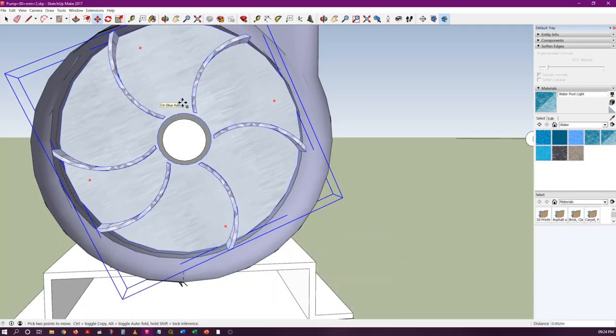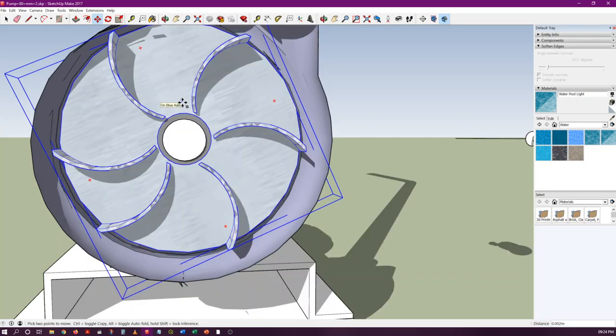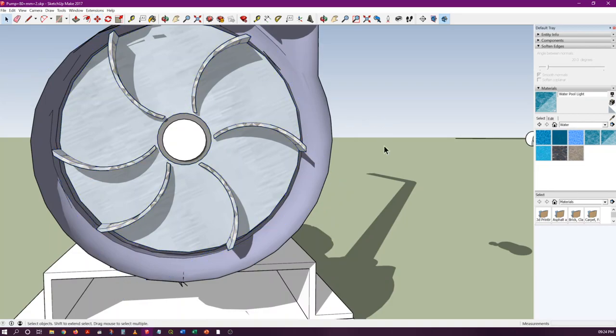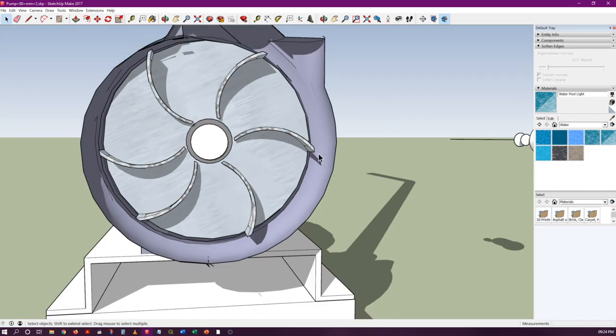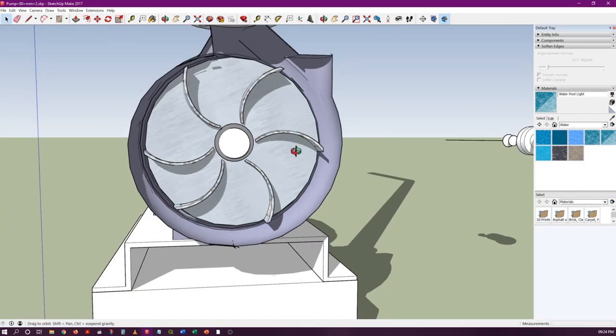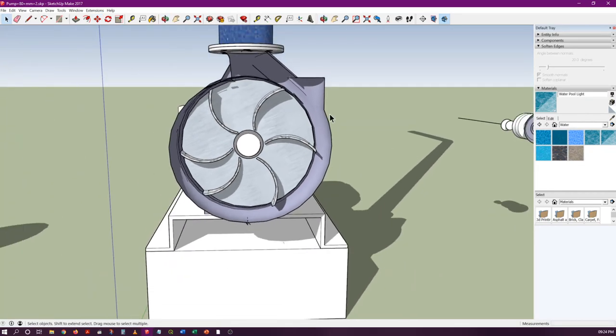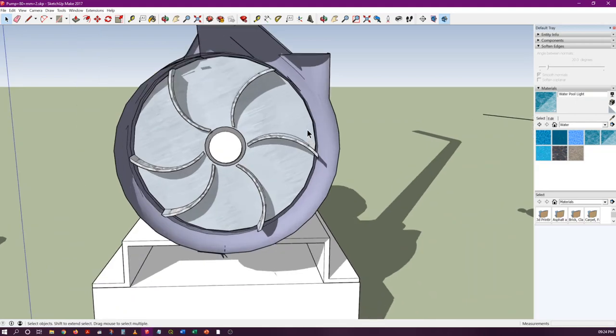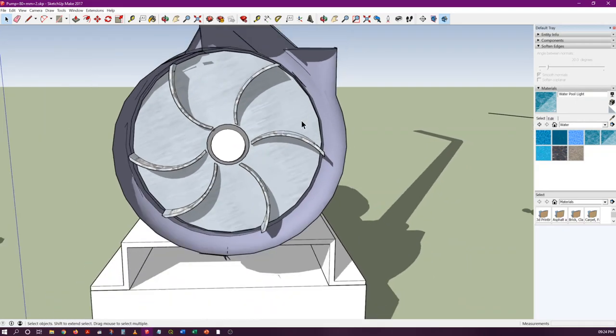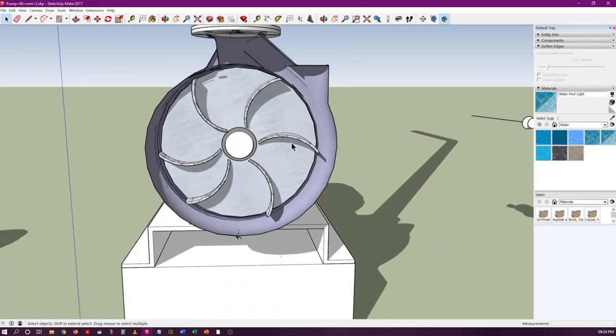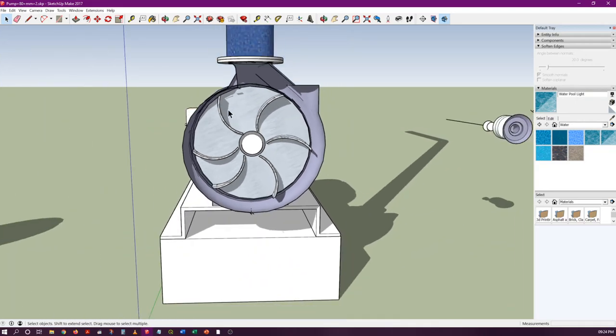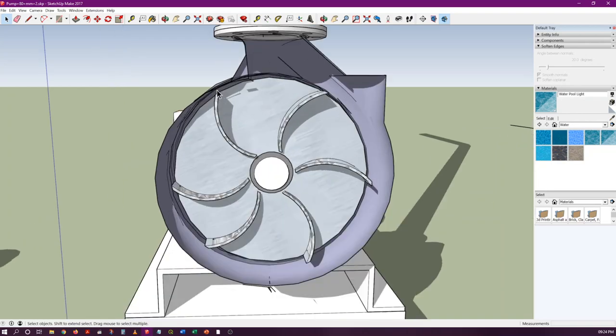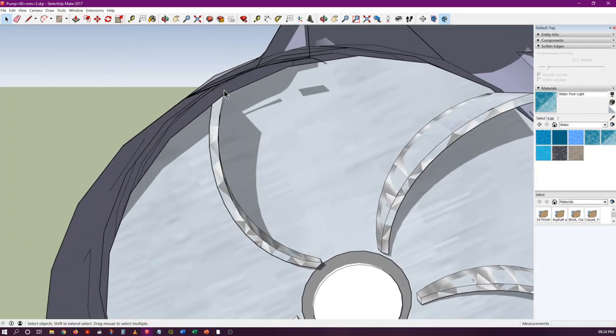It needs to be centered with the shaft that is rotating the impeller. Now if you look at this casing, called the volute casing, you'll notice one thing: on this side, the clearance is very small between the impeller blades and the casing.